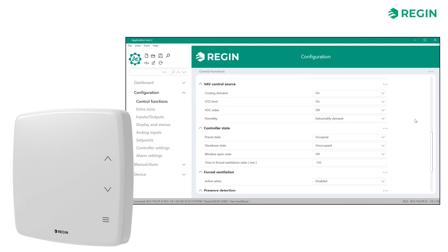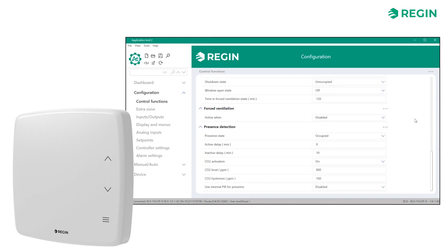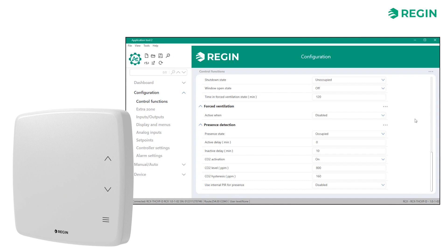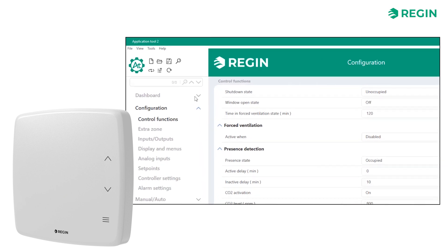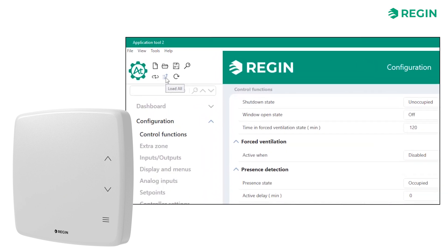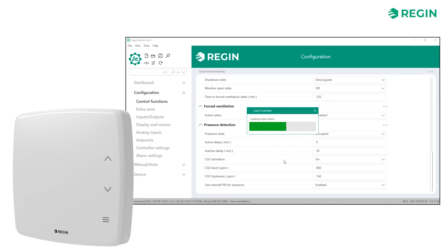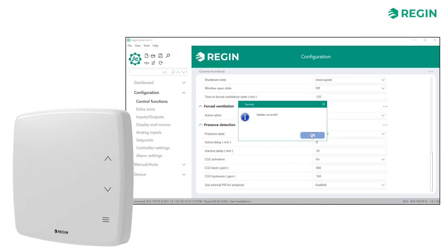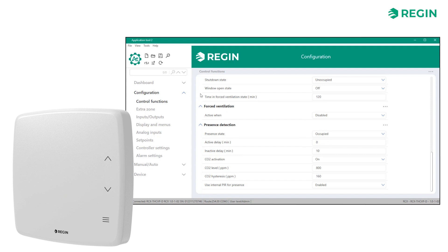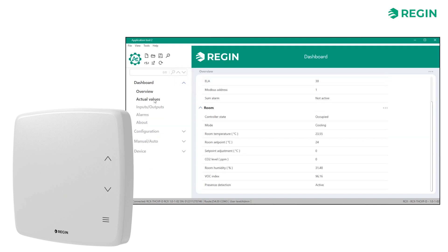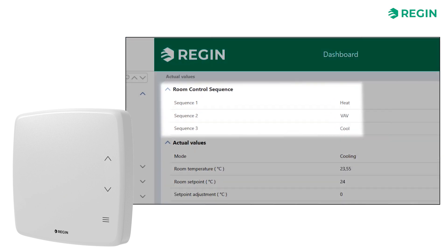Next we can configure the controller's state, as well as decide if we want forced ventilation to be active and what variables to trigger it. For presence detection, let's enable the onboard PIR sensor. Note, however, that no changes have yet been loaded to the controller. To do so, click the Load Configuration icon in the upper left corner. For confirmation, we can go back to the Actual Values page to see that the selected sequences are now running.